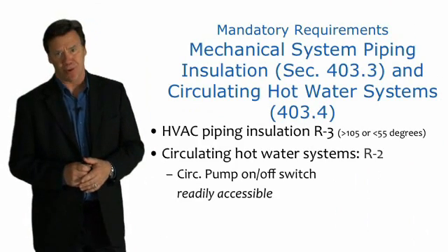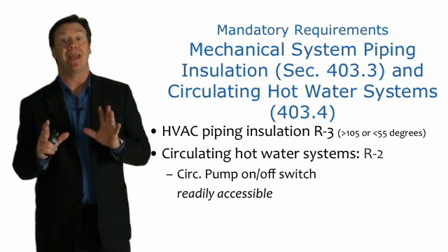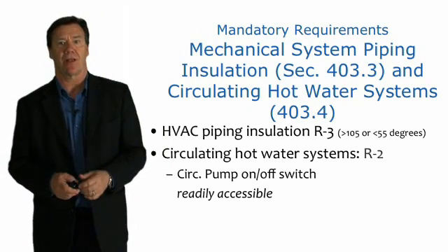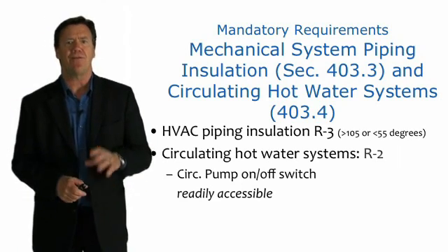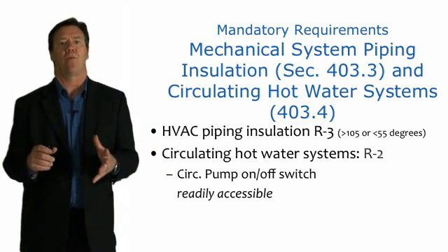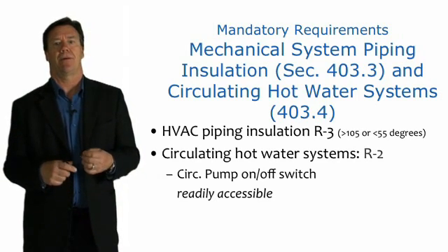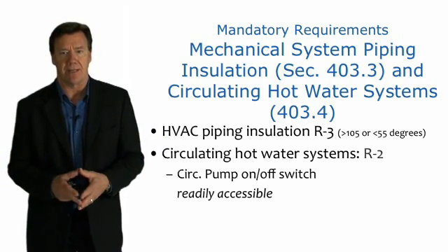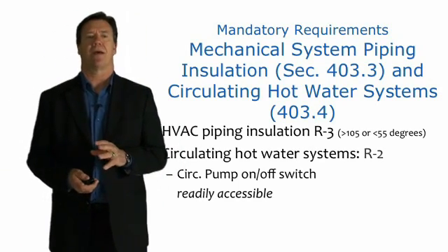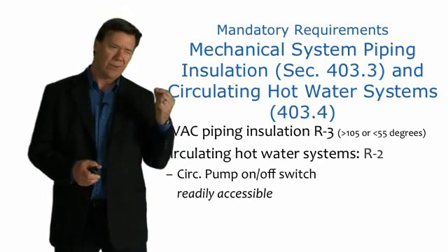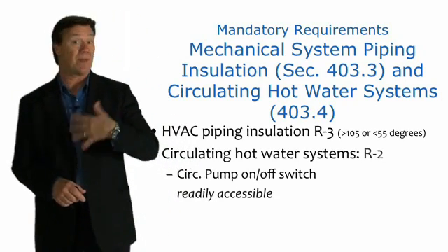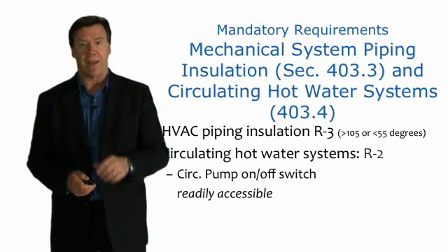Now let's talk about mandatory requirements for system piping and insulation for circulating hot water systems and hydronic systems. HVAC piping for a typical hydronic system with water temperatures of 105 to 55 degrees requires R3 insulation. Typical circulating hot water systems require R2. The circulating pump must have a readily accessible on-off switch. Those are mandatory requirements.